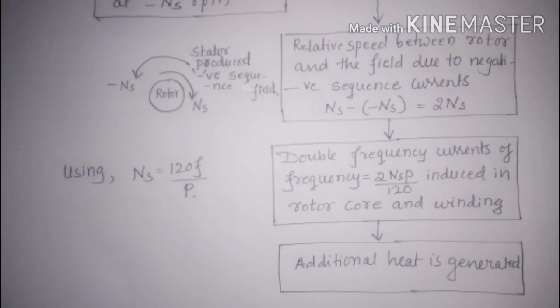This EMF circulates current in the excitation winding, because of which I square R losses occur in the field winding. Not only that, the hysteresis losses and the eddy current losses also appear. It is because of these 3 losses the rotor gets overheated.